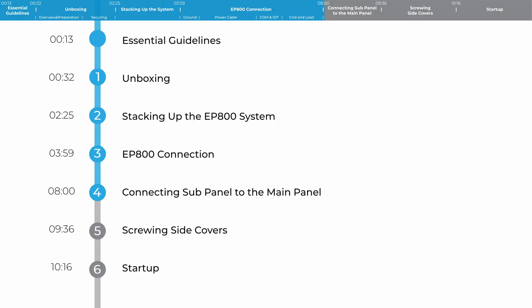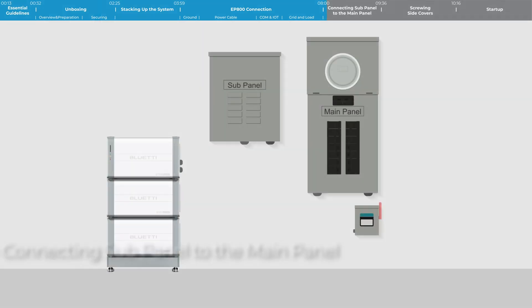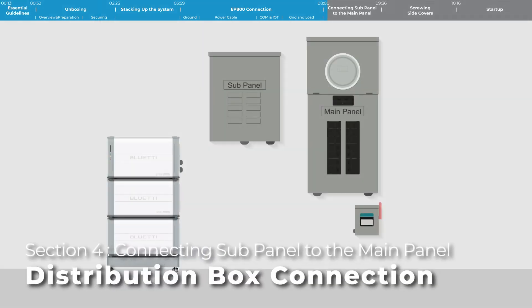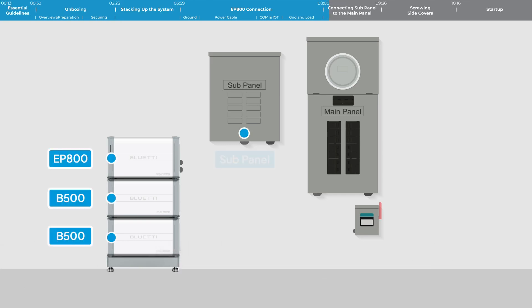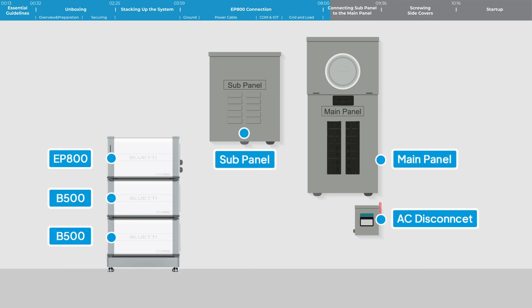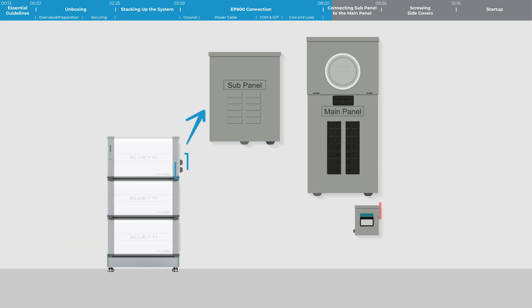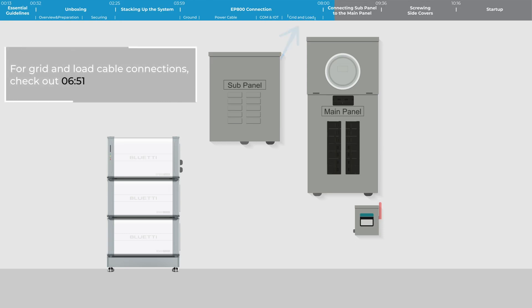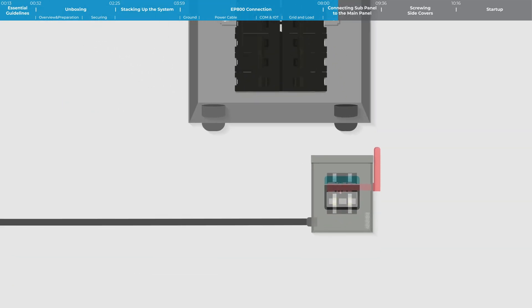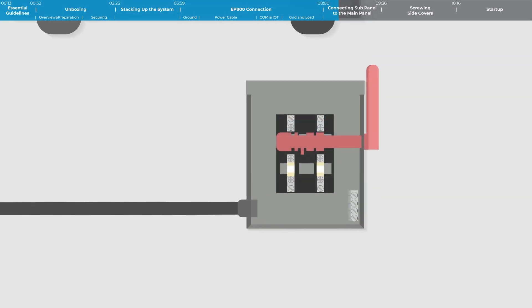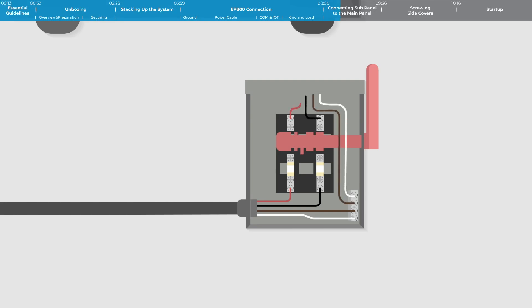Step 4: Connect the EP800's grid cable to the rapid shutdown switch. Attach the red and black live wires to the 2P circuit breaker. Link the white neutral wire and copper ground wire to the ground neutral bus bar.